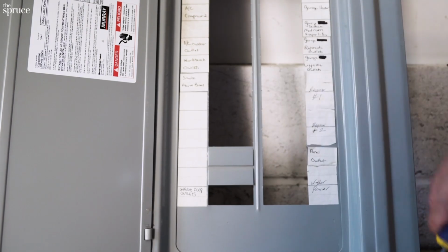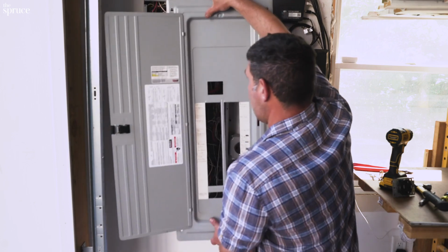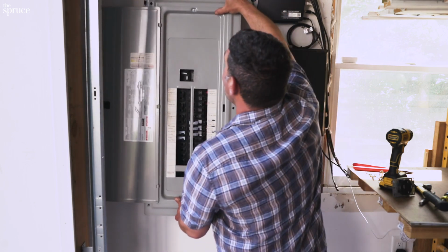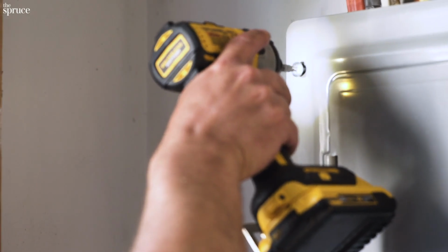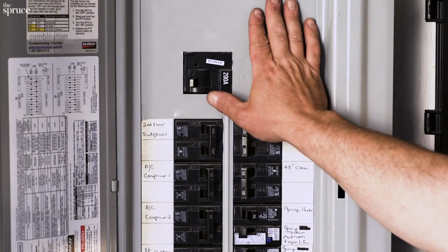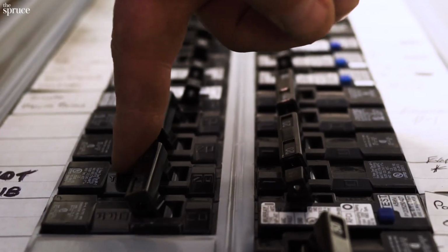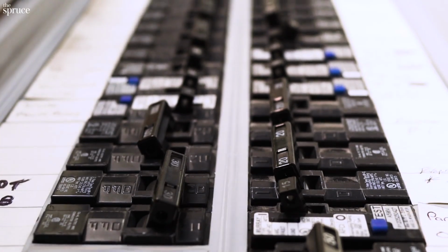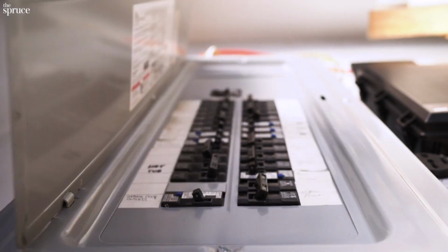The last step is to remove 2 panel twist outs for the new breaker and replace the front cover. Once the cover is on, you can turn on the main breaker to restore power to your panel. But don't turn on the new 240 volt breaker until everything on its circuit is ready for use. So, after your appliance is installed, then you can switch on the new breaker to energize the circuit.